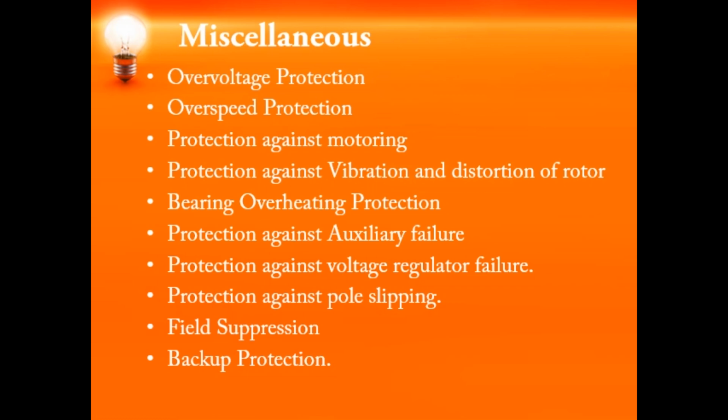Therefore, whenever the rotor is oscillating, it doesn't mean that the relay has to operate, okay? But we need to take care. In some cases, the angular displacement of the rotor exceeds the stability limit, and the rotor slips a pole pitch. In case the disturbance is still persisting, then the relay has to trip.